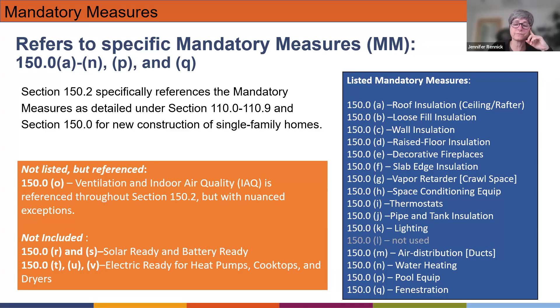When it says you also have to comply with the mandatory measures, they're talking about roof insulation and wall insulation, slab on grade insulation if you're doing a new slab, pipe and tank insulation for water heating systems, certain things for lighting, air duct distribution where applicable, and water heating for electric ready when applicable. But the things that don't come up would be solar ready, battery ready, or other electric ready for heat pumps, cooktops, and dryers. Those would all be associated just with new construction.